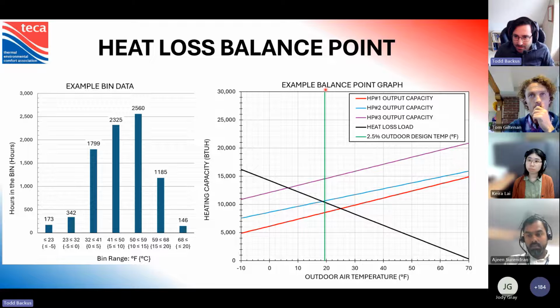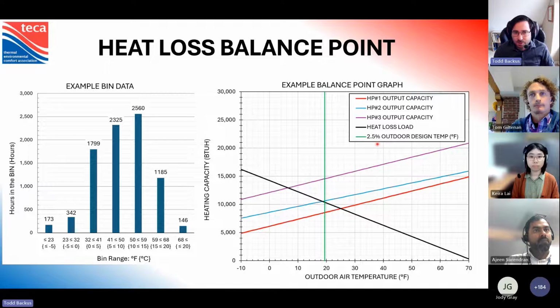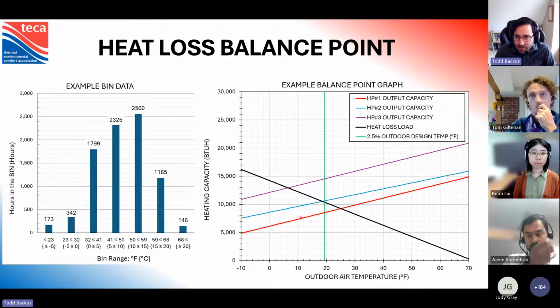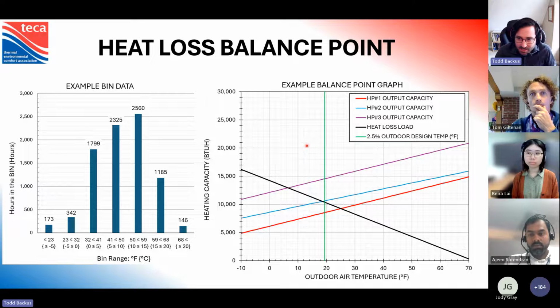From a code compliance perspective, this green line is the 2.5% outdoor design temperature. This is the code minimum that your heating system has to hit. So heat pump 2 actually meets that. Heat pump 3 exceeds it. You could use heat pump 1, but you would need some other form of heating to make up the difference here. One thing to keep in mind here: the 2.5% outdoor design temperature is the lowest temperature that you're going to see 97.5% of the year. So there are still 2.5% of the time you are actually going to be in this region. And that's why personally I use the 1% outdoor design temperature, but the code minimum is 2.5%.